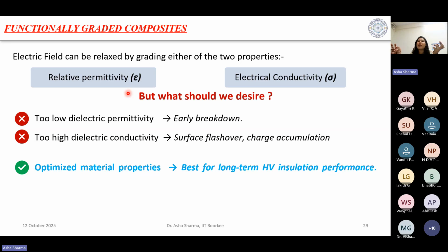The reason is these insulator strings are exposed to the environment - one end connected to the conductor, the other grounded, exposed to the environment. So conductivity will also be there, which relates to the tripping of transmission lines because of dry band formation. So can we balance the electrical conductivity and permittivity, so that we can reduce the electrical stress at the end of the high voltage insulator string?